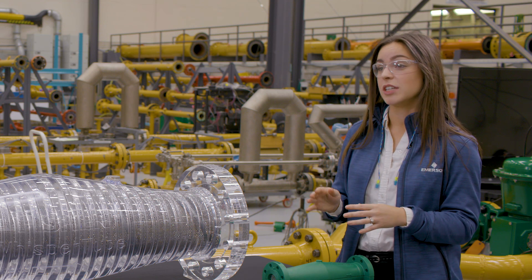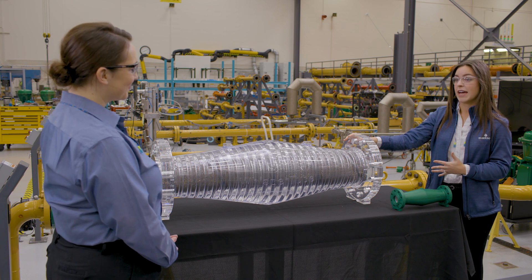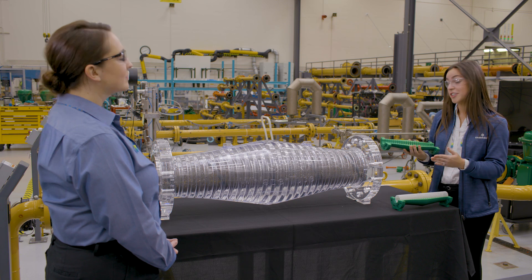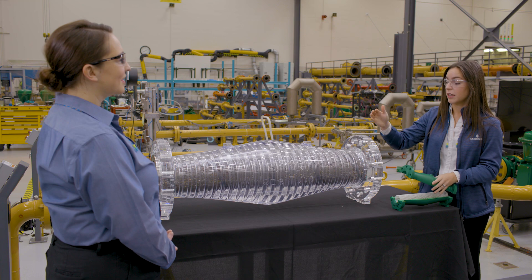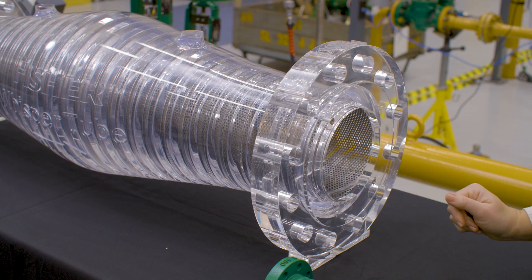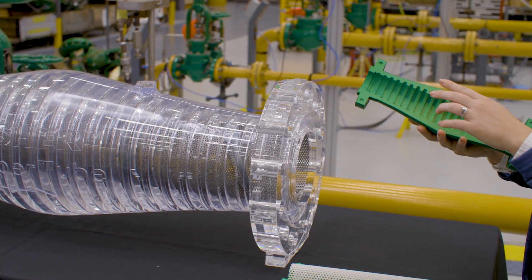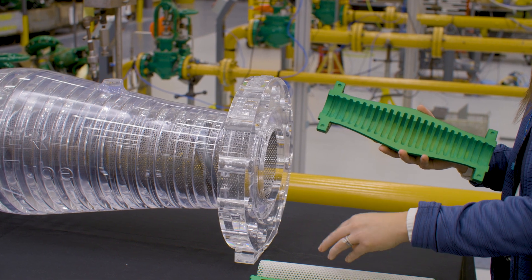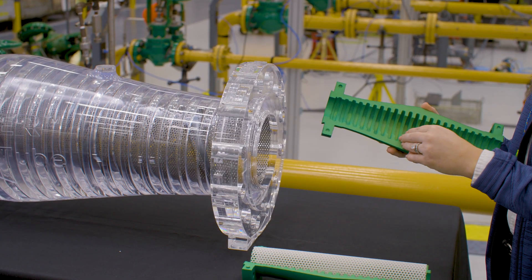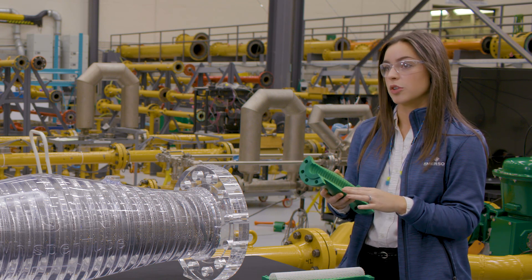This is very unique because no other technology can achieve this today without acoustic packing. I have two models here to help explain: a life-size six-inch Class 600 Whisper Tube, and a scaled-down three-inch model with a cross-sectional view so you can see inside. One of the key features is the cavities cast internal to the body, and the screen on the inside. The screen serves as the primary flow path for the process, and the cavities are where the magic happens. As the process flows through the Whisper Tube, acoustic waves propagate through the screen and into the cavities. Destructive interference occurs when the waves reflect back at each other off the cavity walls, resulting in reduced noise propagation downstream. Each cavity is of a different depth, letting us target a different frequency range of noise, so we achieve broadband noise reduction.